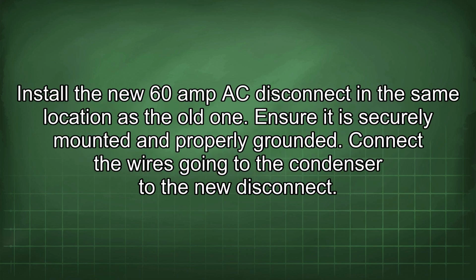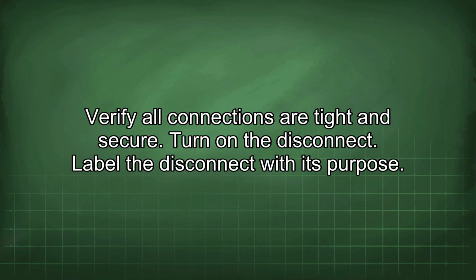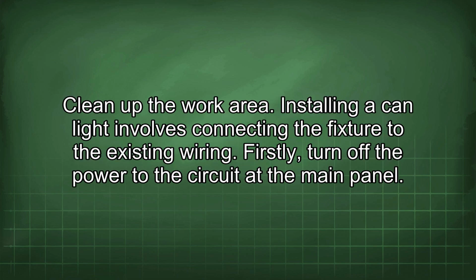Install the new 60 amp AC disconnect in the same location as the old one. Ensure it is securely mounted and properly grounded. Connect the wires going to the condenser to the new disconnect. Verify all connections are tight and secure. Turn on the disconnect. Label the disconnect with its purpose. Clean up the work area.